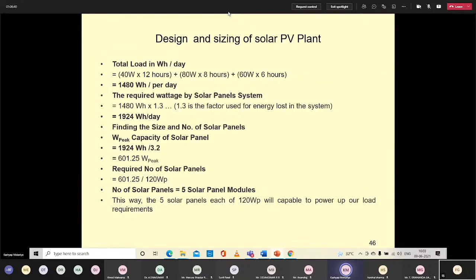You have to consider so many other parameters, because if your panel generation factor is accurate, you will get some accuracy at the designing stage, and then you get how many solar panel modules there will be. For sizing of the inverter, it is very straightforward. Whatever the load capacity in wattage is, you have to go 25% greater than that for considering losses in the inverter, and for 180 watt, you have a 225 watt inverter.